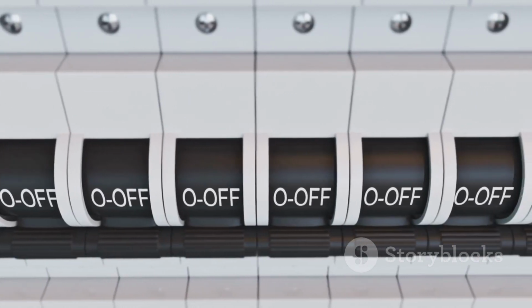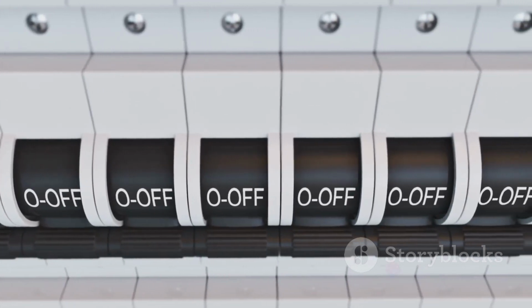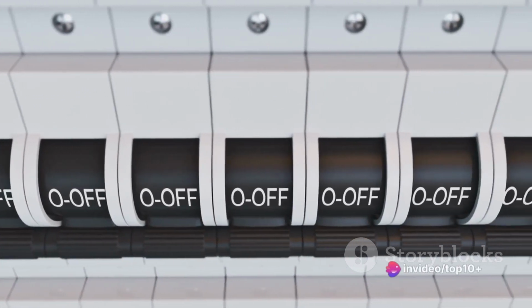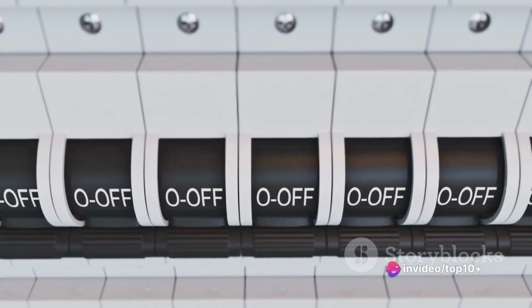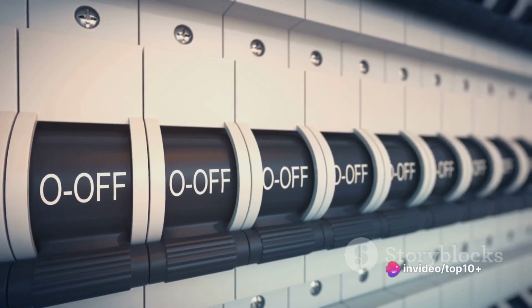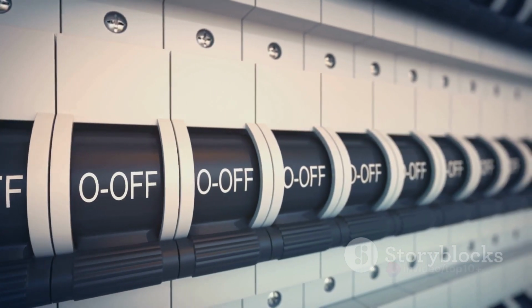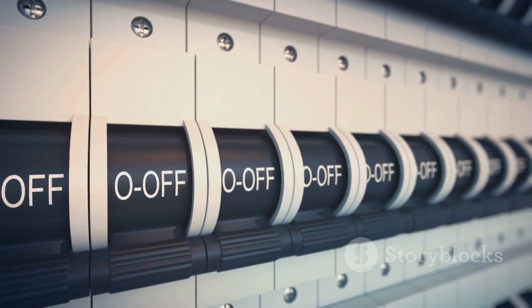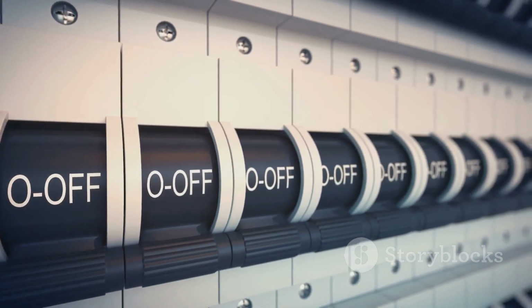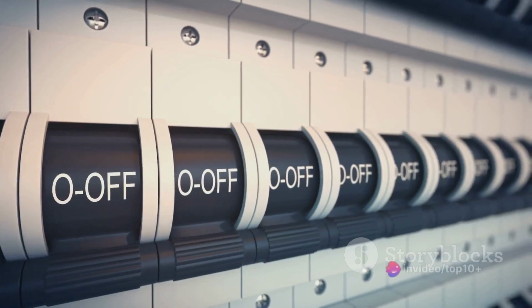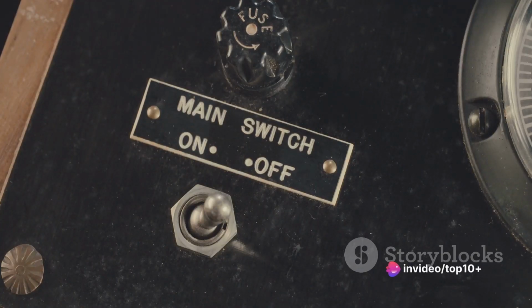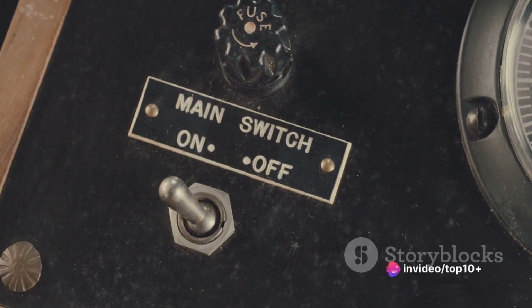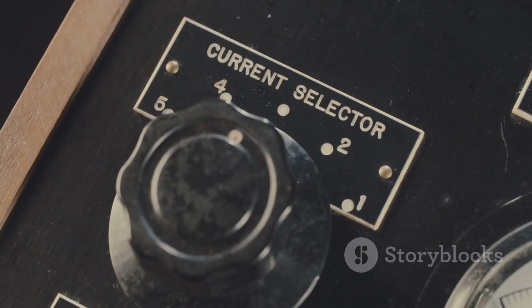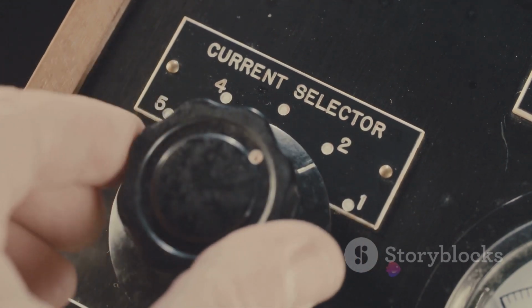The second step is tripping. This is where the MCB takes action. When the bimetallic strip bends due to heat, or the electromagnetic coil is activated by a current surge, it triggers the tripping mechanism. This mechanism is connected to a switch, which is in the on position when the circuit is functioning normally. But when the tripping mechanism is activated, it pushes the switch to the off position. This is a manual switch, which means once it's tripped, it won't go back to the on position on its own. It requires a manual reset.